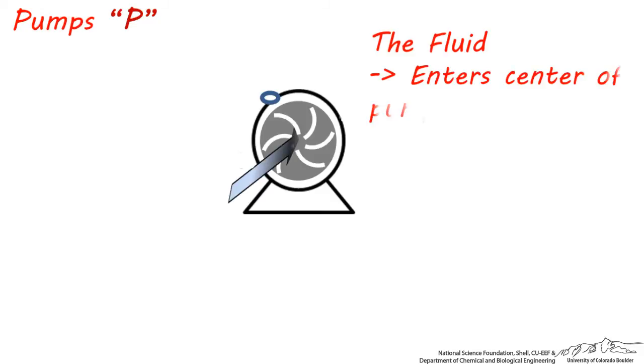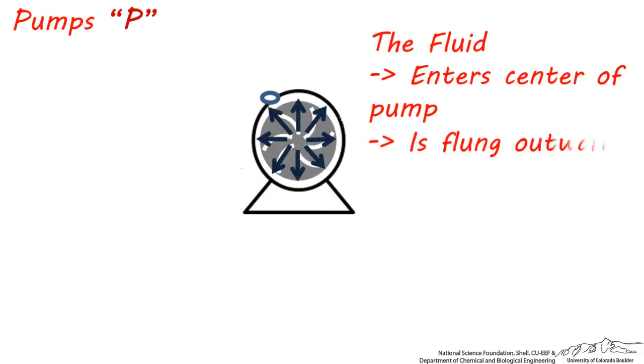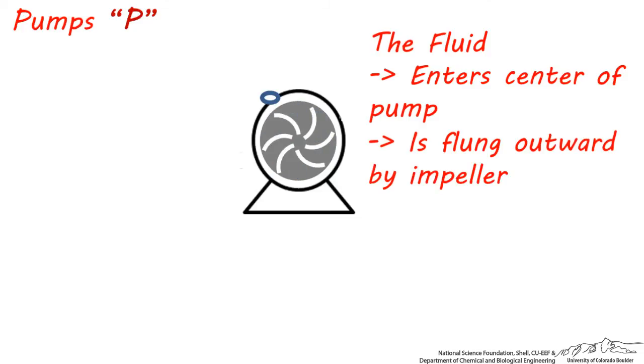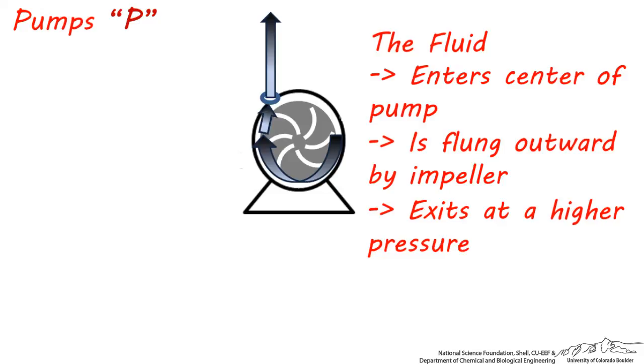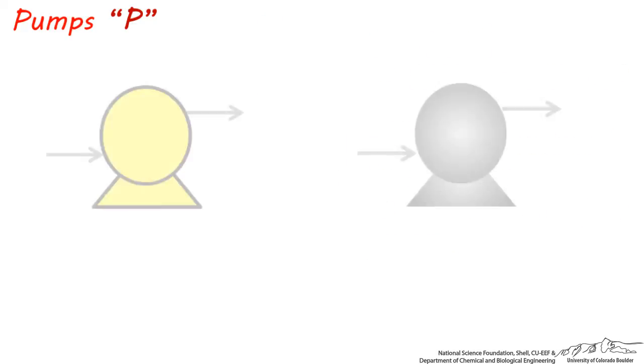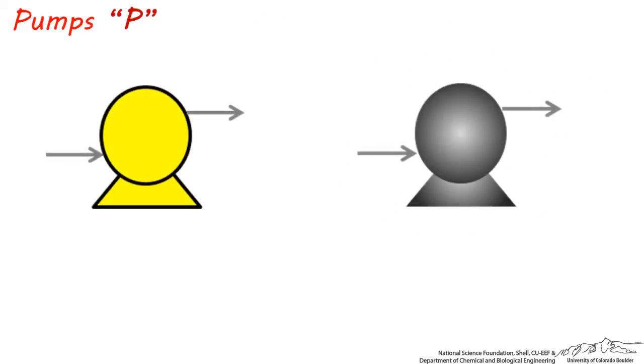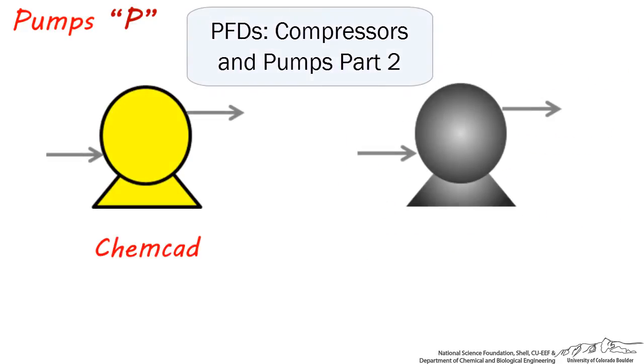The fluid enters the pump in the center, and the impeller blade flings the liquid outward towards the casing. This work being done on the fluid results in an increase in pressure as the fluid leaves the pump. This pressure increase is critical for moving fluids upward or across long lengths of piping from one process unit to another. In terms of pump symbols in simulation software, this pump symbol is what's commonly used in ChemCAD, and this is the symbol used in Aspen.